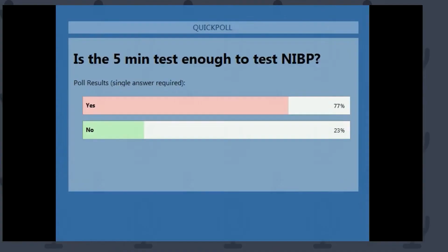So 77% of you thought that the parameters that we evaluated in the demo for NIBP was enough to be satisfied that NIBP safety and performance is okay. 23% of you said no. And I kind of lean to that group that says no. And here's why. Because NIBP accuracy can never be determined by dynamic simulation. The only thing that can be determined by dynamic simulation of NIBP is repeatability, and that's all.